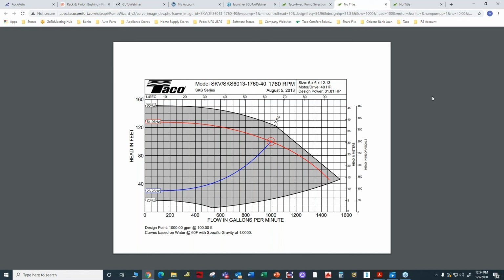Now it turns out that this pump can use a function called ProBalance. ProBalance allows you, through a couple of keystrokes on the keypad, to find the actual pressure drop at the design flow. In this case, we estimated the pressure drop through calculations to be 1,000 gallons per minute at 100 feet. What if in reality it was 80 feet? Well, the pump can find that pressure drop at the design flow.